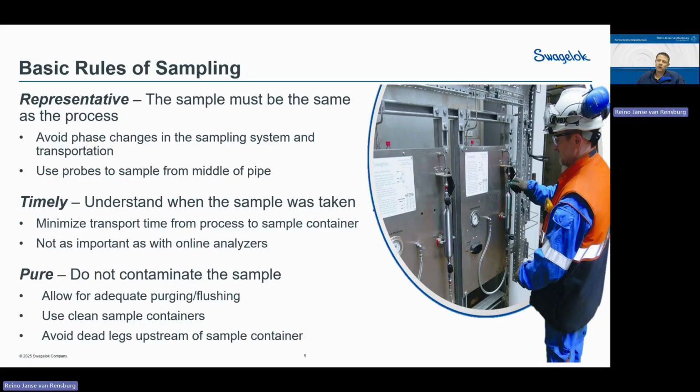Then you want it timely. You want to understand when the sample was taken. There's no point taking a sample when you only evaluate it two days later, for instance. Then it doesn't really tell you what's going on in your process now. So you also need to make sure that the sample point and where it's situated gives a sample that is representative of what's happening in your system now.